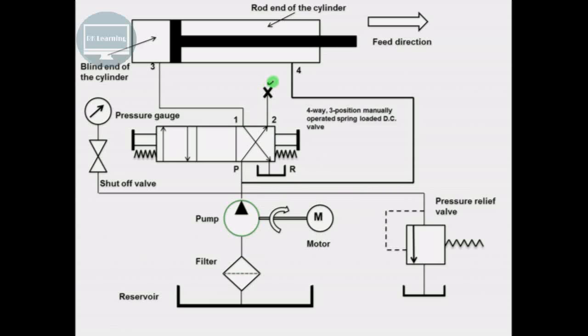Since port 2 is blocked, fluid enters into the rod end of the cylinder and causes the backward motion of the piston rod. The liquid from the blind end of the cylinder from port 3 goes to reservoir R.